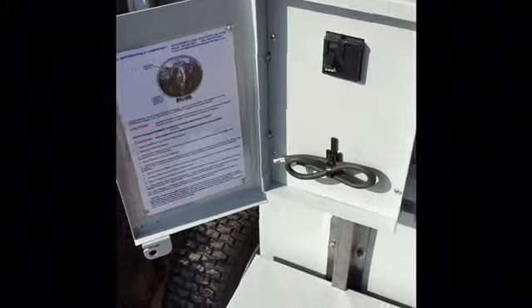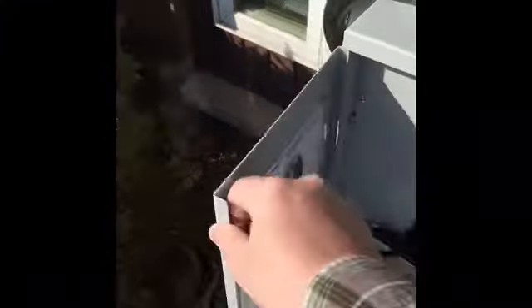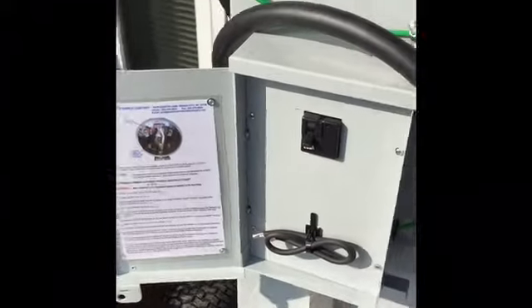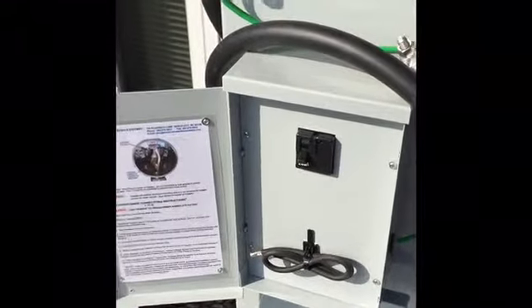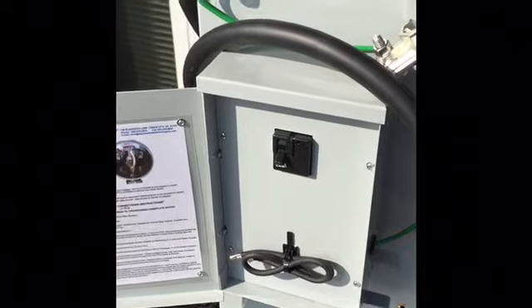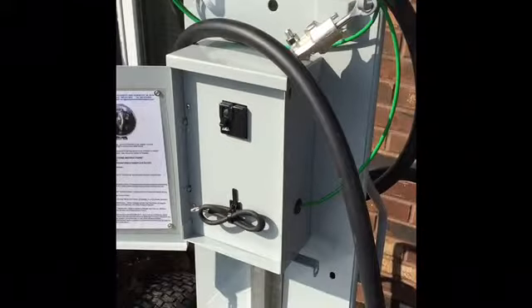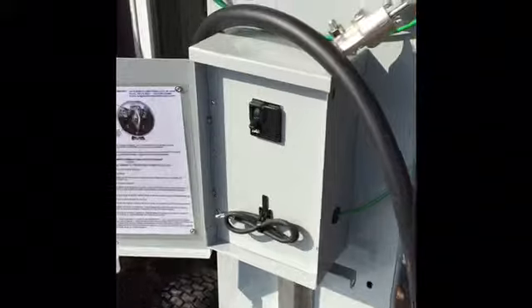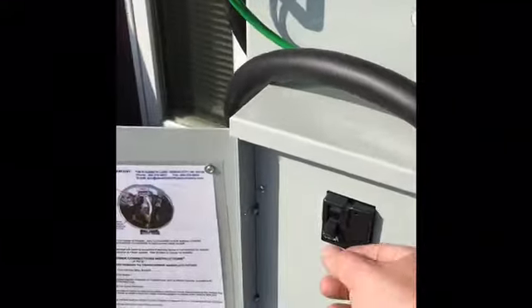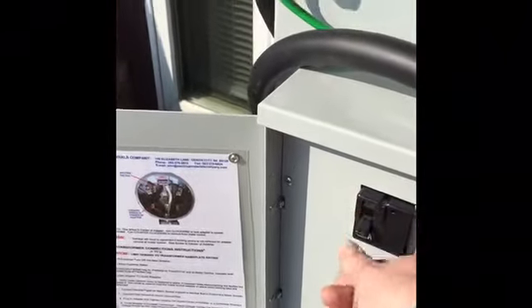And then the next thing to do is to open up the breaker panel here on the quick service restore. And basically what you want to do then is open up the main breaker right there. In this case we have a 200 amp breaker. This is a 25 kVA unit. So we go in, it's already in the off position there.